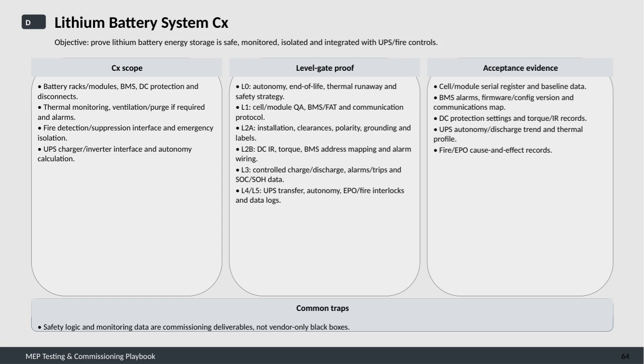Acceptance evidence is critical and includes records such as serial registers and baseline data of cells and modules, BMS alarm logs, firmware versions, and communication maps. Settings for DC protection are documented alongside torque and insulation resistance measurements. UPS autonomy and discharge trends are analyzed in combination with thermal profiles, while cause and effect records for fire and emergency power-off events are maintained. A common trap to avoid is treating safety logic and monitoring data as vendor-only black boxes. This data and these controls must be part of the commissioning deliverables to ensure transparency, safety, and reliable operation of the lithium battery system.